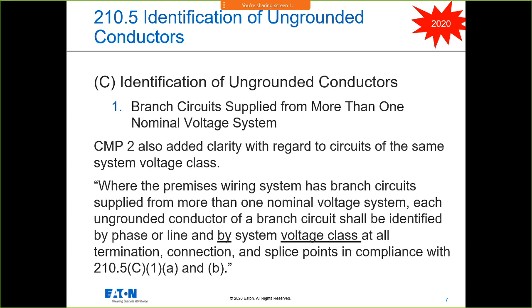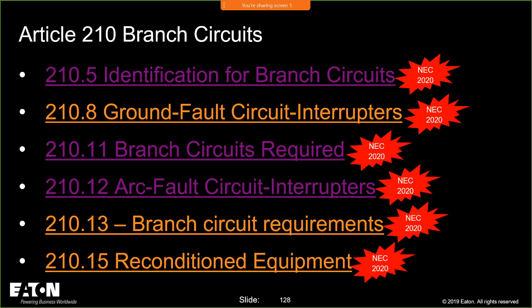This is sort of what we did. This was the 2020 change: identify by system voltage class at all termination connections. I think we're still struggling with 210.5. We're still seeing public inputs trying to add clarity to this because of the concern, at least what I'm perceiving, about having to mark everything in that facility the moment you bring a different voltage class into the structure.